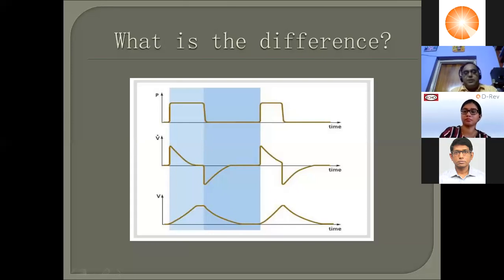Number one. Let's go to the flow time scalar. Here also we see, yes, it is longer, it is shorter, but there is one more difference, and that's a very significant difference. Here it is touching the baseline, whereas here it is not touching the baseline. It has not touched the baseline, but my expiration has started. So what is this breath? This is what we call a supported breath.